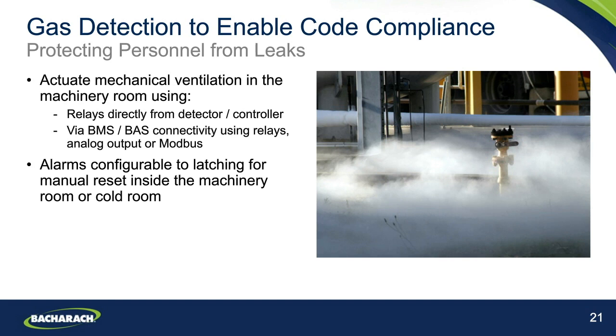And of course, we do want to be looking for alarms to be configurable such that they can be set to latch for a manual reset from inside the machinery room or cold room. And what we mean there by latching is that when an alarm state is in place, it requires that manual reset. It doesn't automatically come out of alarm if that alarm condition is removed. And it also means that we shouldn't be looking for something that you can unlatch and disable an alarm from outside of the monitored space, because the code is quite clear that that should be done from within the space where the detector is.